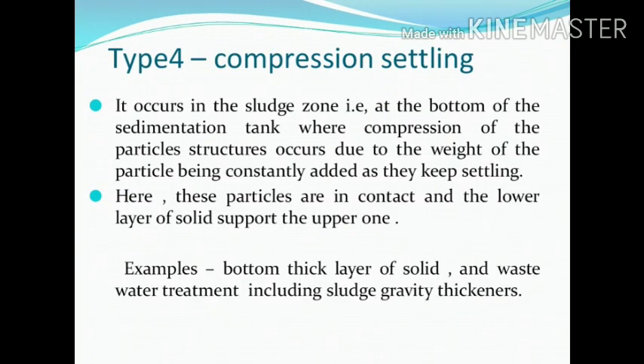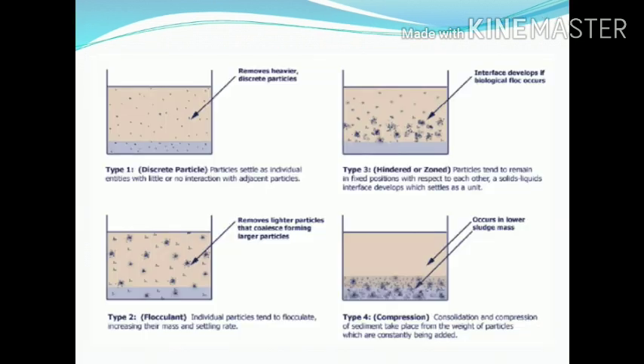Type 4 is compression settling. Compression settling refers to settling in which the concentration of particles is so high that the particles are in physical contact with each other, resulting in the formation of a structure where the lower layer supports the weight of the upper layer. Further settling occurs due to compression of the whole structure of particles, accompanied by squeezing out of water from the pores between the solid particles. Examples include the bottom thick layer of solids in wastewater treatment, including sludge gravity thickeners.